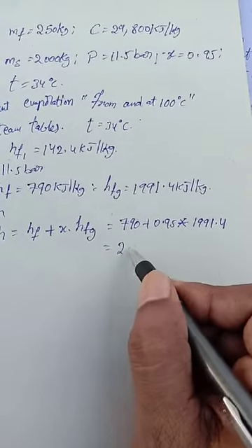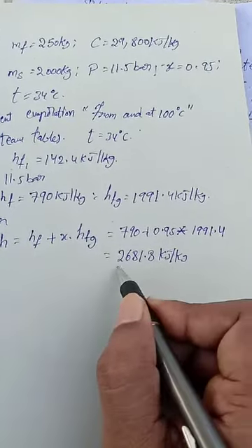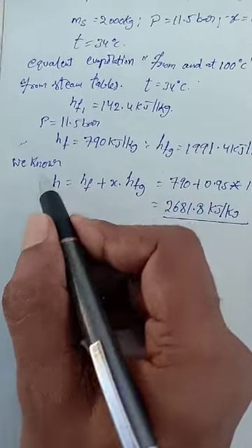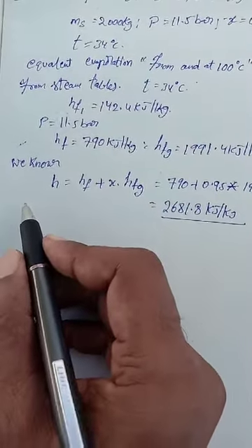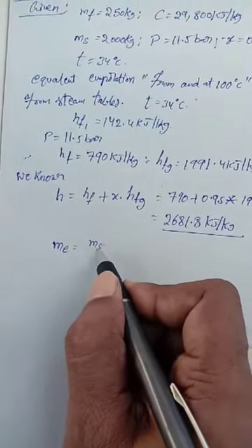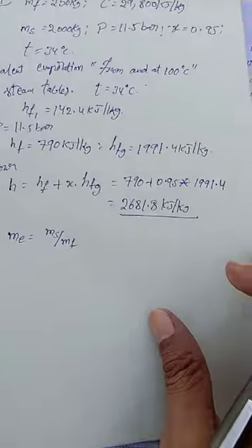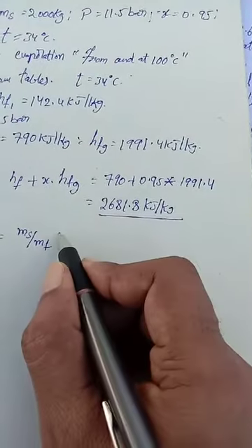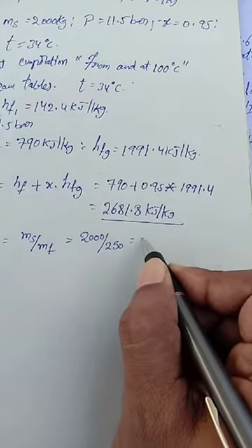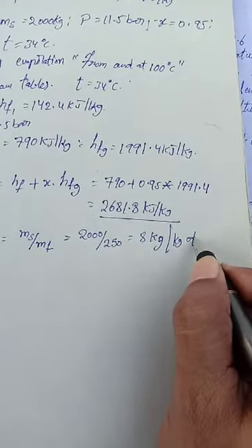Now calculating this, we get the enthalpy or total heat in kilojoules per kg. Next, the mass of water evaporated per kg of coal: Me = MS divided by MF. Substituting the values, Me = 2000 divided by 250, which gives 8 kg per kg of coal.